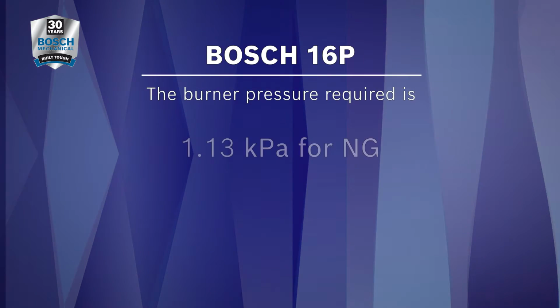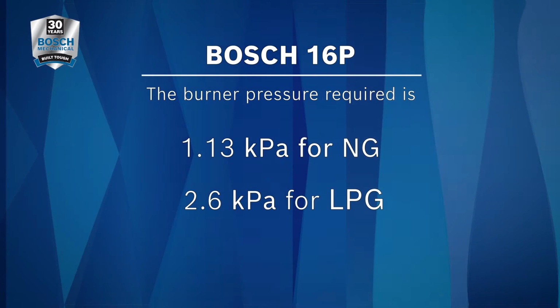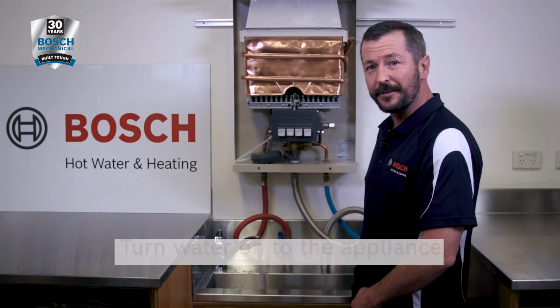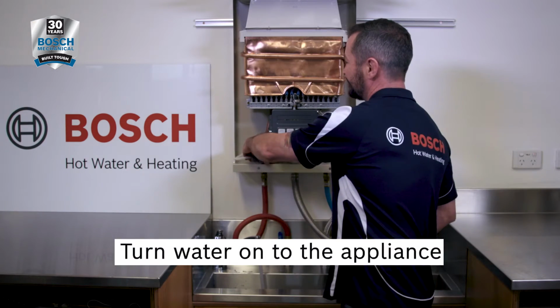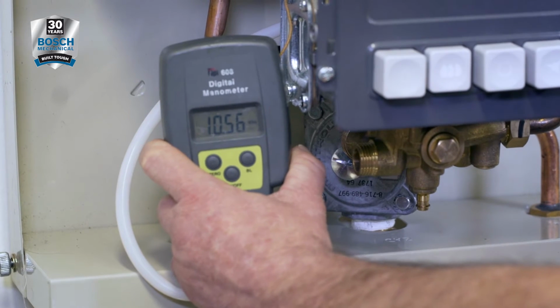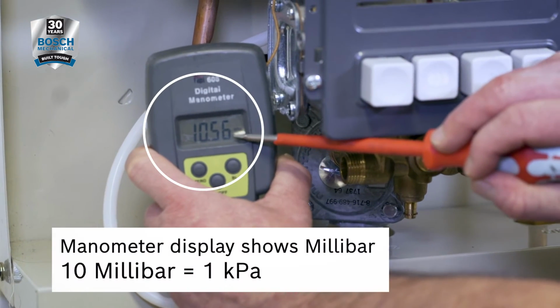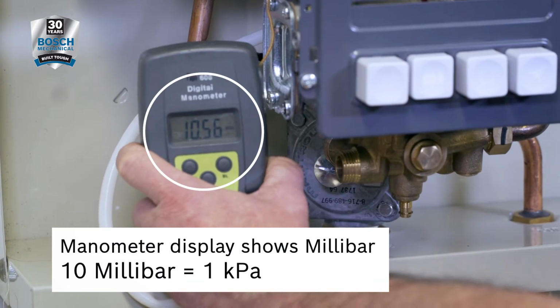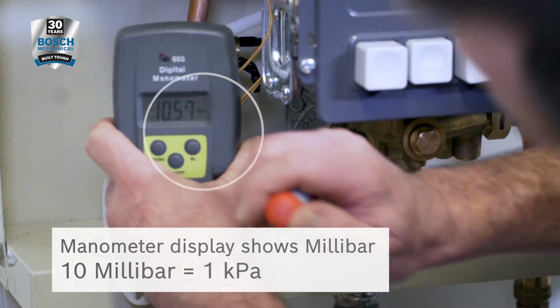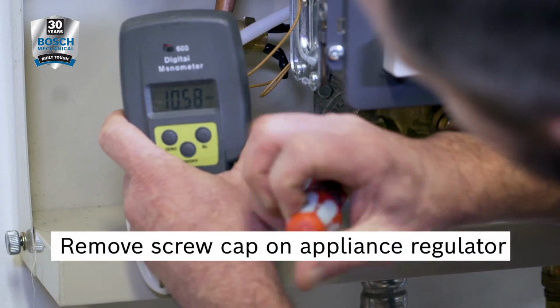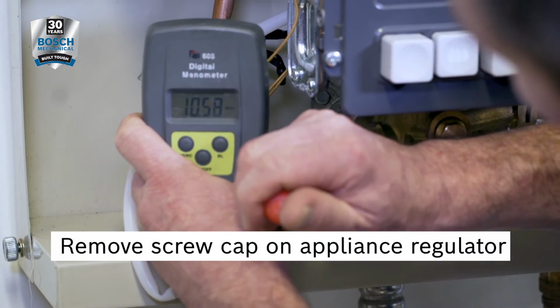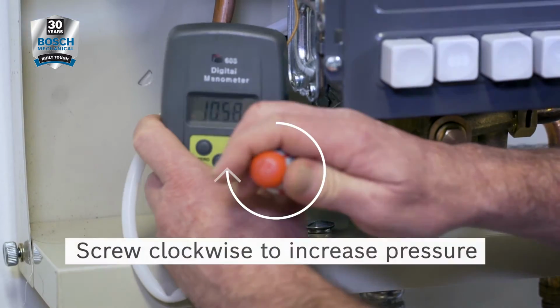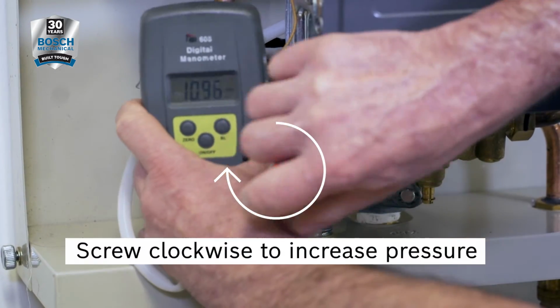The minimum gas pressure required for natural gas is 1.13 kPa. Turn the water on to the appliance and check your gas pressure. This appliance here is natural gas, so as you can see our gas pressure is a little bit low. To adjust our gas pressure, access the adjustment screw on the regulator. Turning the adjustment screw in clockwise will increase the pressure, anti-clockwise will decrease the pressure.